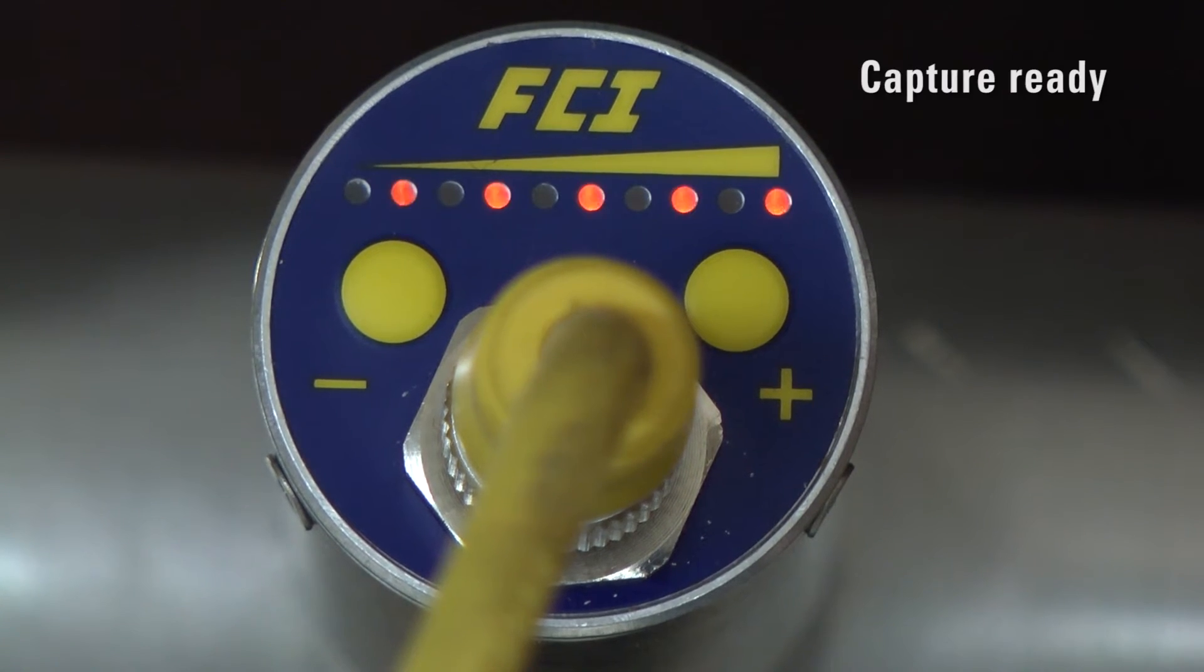The LED pattern will change to alternating LEDs flashing, indicating the unit is in capture ready mode. Throttle the flow to the desired alarm setpoint, or if not possible, adjust the flow as close as possible to the desired setpoint.